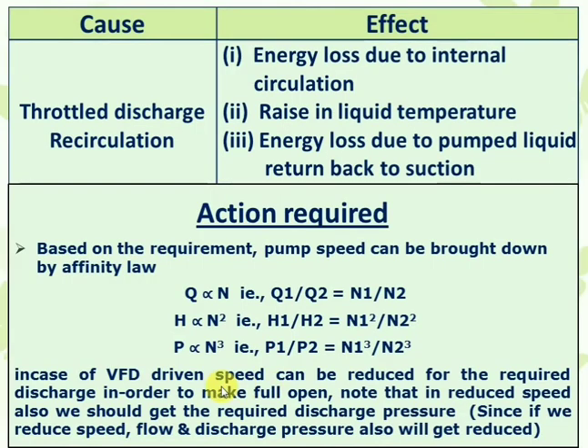Normally, we may not require the complete discharge flow being pumped. So we throttle or pinch the discharge valve. What happens due to this is that the liquid gets internally circulated and there is energy dissipation because we are not completely drawing the liquid. If we throttle the discharge, current will come down, but energy losses will occur due to that extra liquid being pinched — it circulates and increases the liquid temperature. If the discharge valve is throttled more, cavitation can occur, causing pitting in the impeller and casing, leading to damage.